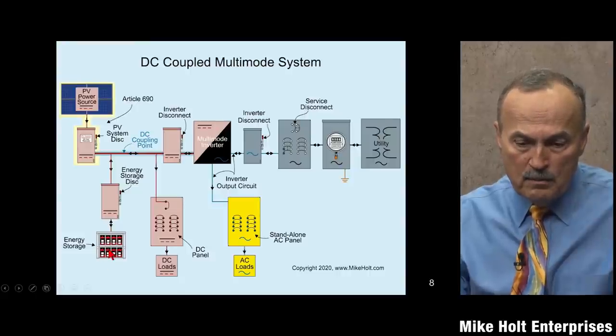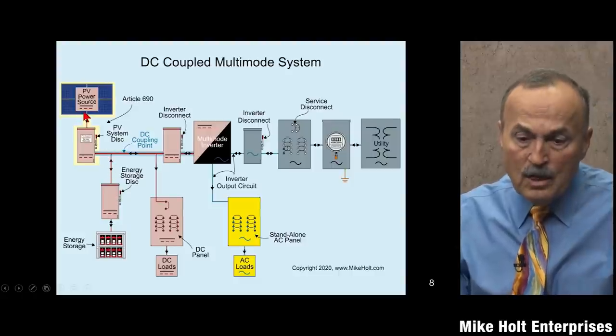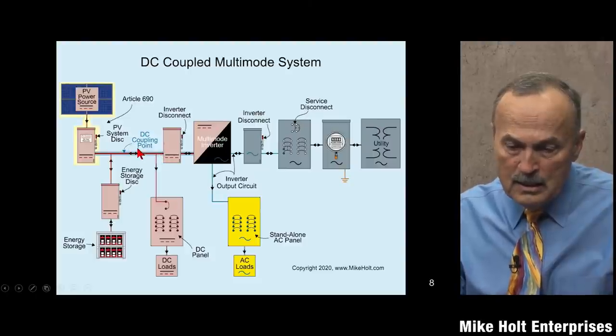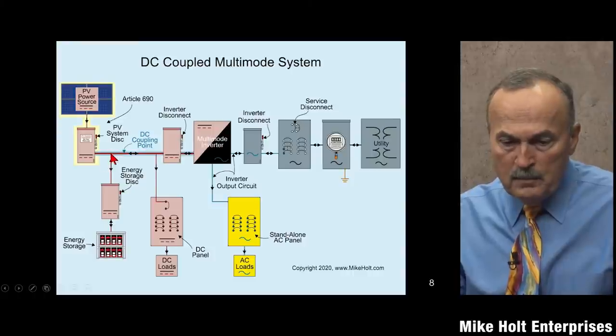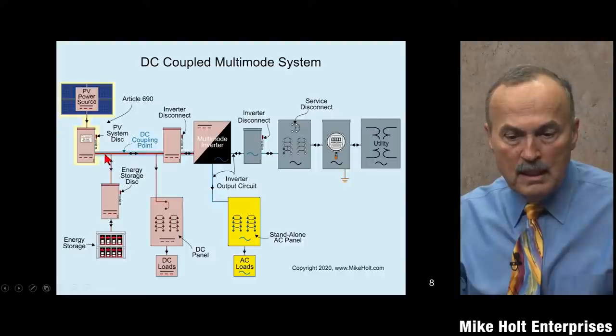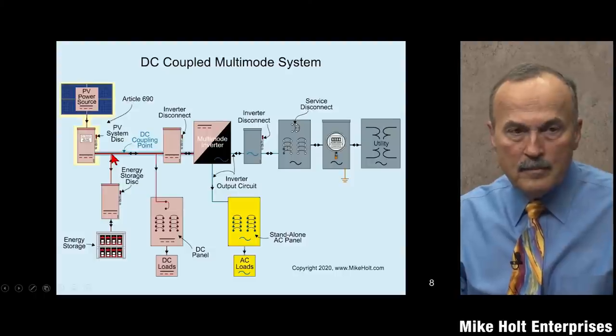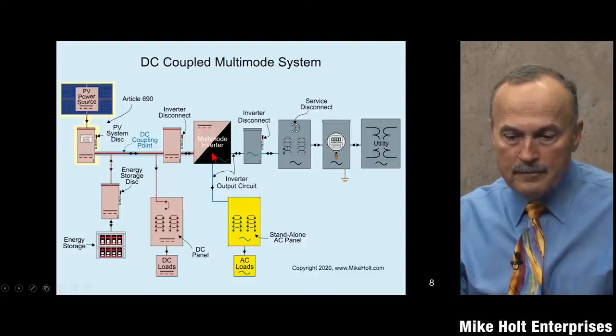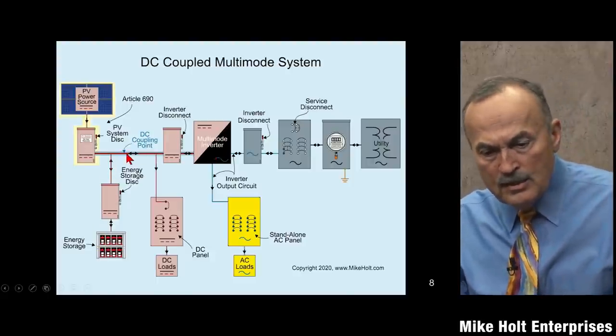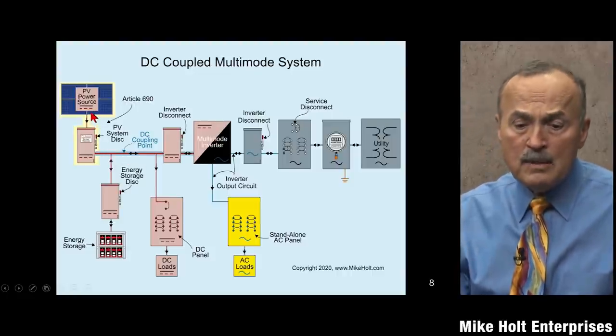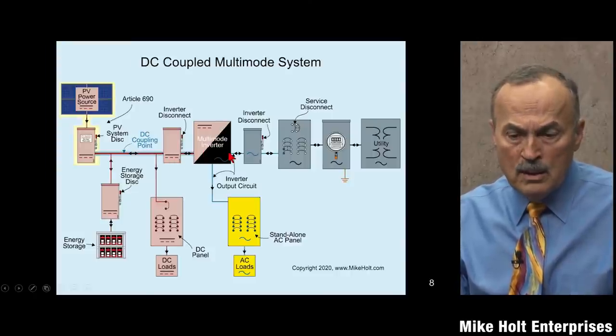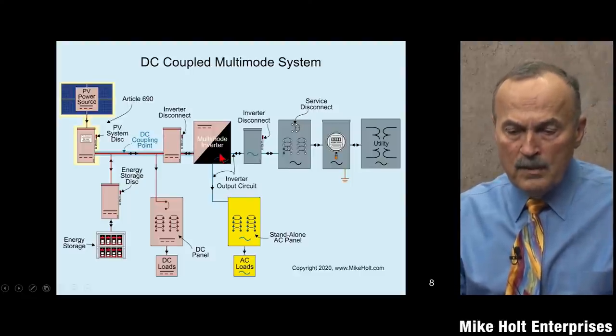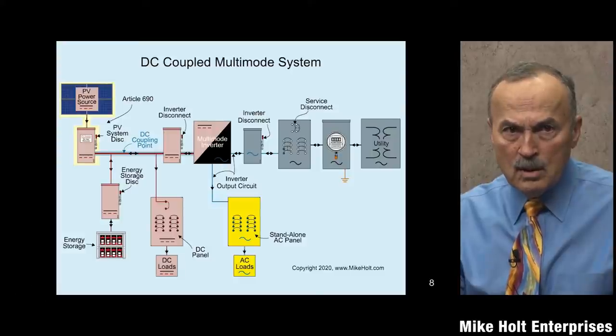There are times when power is needed from the battery, so electrons can go back the other direction. They can't go back up to the power source since it only goes one direction, so they move over to the point of DC coupling - think of it as a DC bus. You're supplying power to a DC bus and the inverter operates off that bus. It has two sources: solar and energy storage.